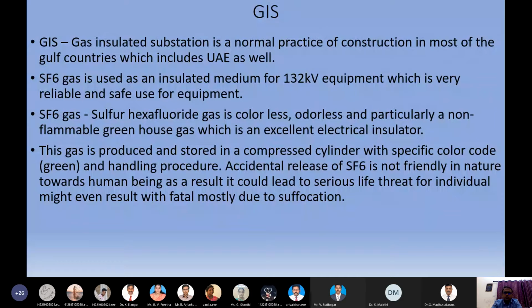This has been recommended by most of the manufacturers, so-called ABB, Hitachi, and GE, General Electric also. But the main concern is this gas is not human friendly. It needs to be handled in a very particular way, because it will be filled in a compressed gas cylinder, which will be initiated in the GIS equipment using a machine called DILO machine. With the accumulator pressure, it will be installed. But any kind of release of this gas or accumulation by a human being will result in maximum fatality. So the handling and initiating procedures will be done by trained people from the manufacturer, whoever is giving the GIS equipment for us, or for the contractors, or for the clients, we can say.